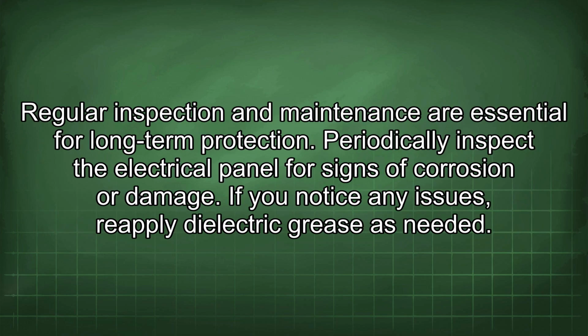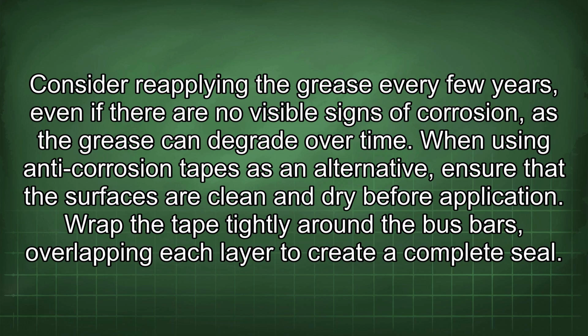Regular inspection and maintenance are essential for long-term protection. Periodically inspect the electrical panel for signs of corrosion or damage. If you notice any issues, reapply dielectric grease as needed. Consider reapplying the grease every few years, even if there are no visible signs of corrosion, as the grease can degrade over time. When using anti-corrosion tapes as an alternative, ensure that the surfaces are clean and dry before application.